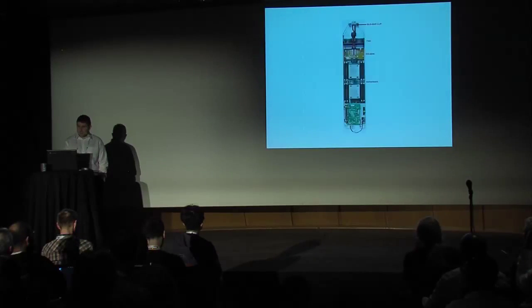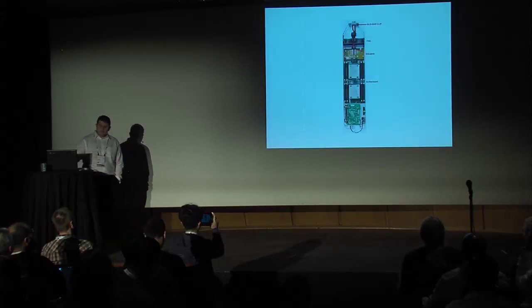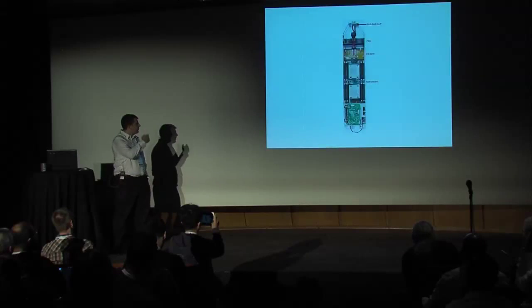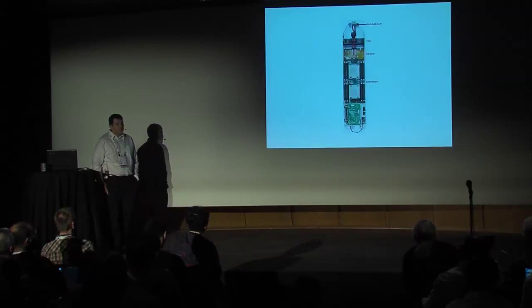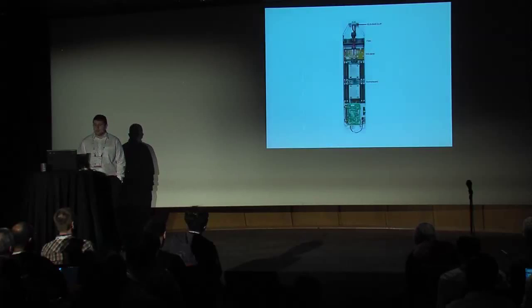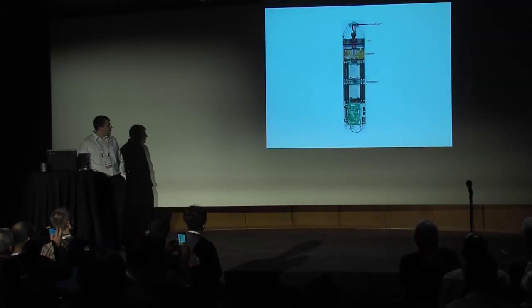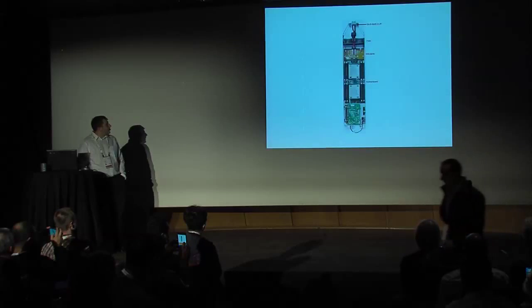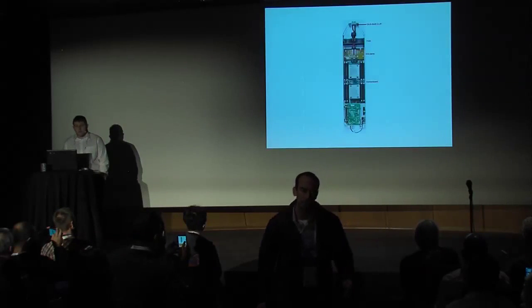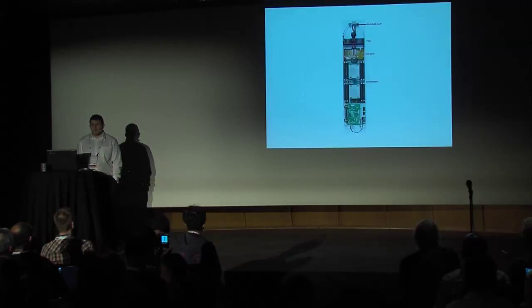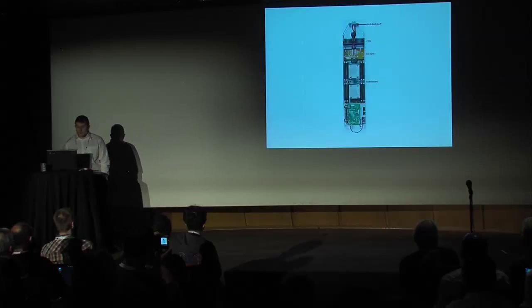So let's meet the servers. Specifically, OpenCompute is a family of servers. The ones I'm talking about now are the Winterfell. For those of you who are familiar with servers, this may look a little long and skinny. There's actually three of them side by side in the rack. The front is your I/O, your system boards, CPUs, a connector in the back to a bus bar. So all of the power supplies and cooling, for the most part, is outside of the server itself. It's driven from the rack.